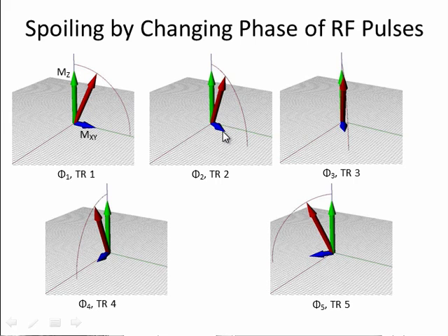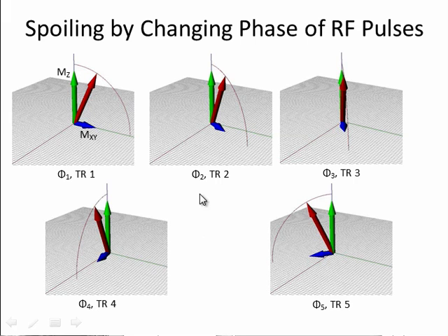At the second TR, the phase of the RF pulse has changed — not the flip angle, which remains the same — so the direction of the transverse magnetization is now in the X-Y plane, not directly on the Y axis. At the next TR we have a different phase, and so on. This series of events where the RF phase is changed is called phase cycling. Usually the phase is changed as a quadratic function — there is a specific equation which gives you the optimal spoiling by this method.